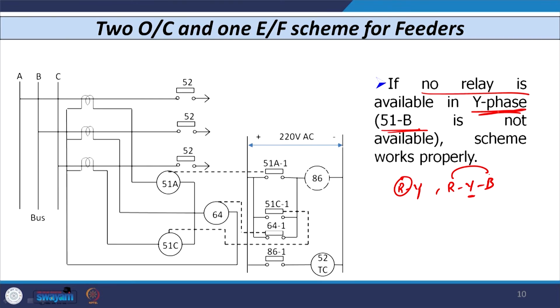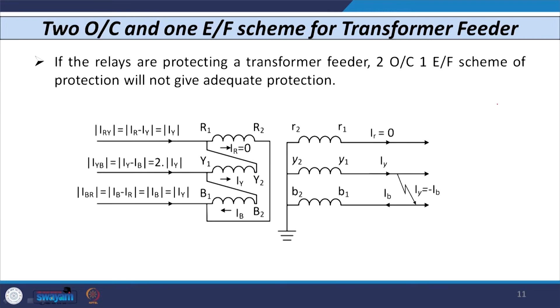Consider an example: in Y phase, there is no unit (51B has been removed) and we use the two overcurrent, one earth fault scheme. Now suppose a Y-B fault occurs on the secondary (star) side of the transformer. In case of a Y-B fault, the current IY equals minus IB and ideally IR equals 0, so IR = 0 and IY = −IB.